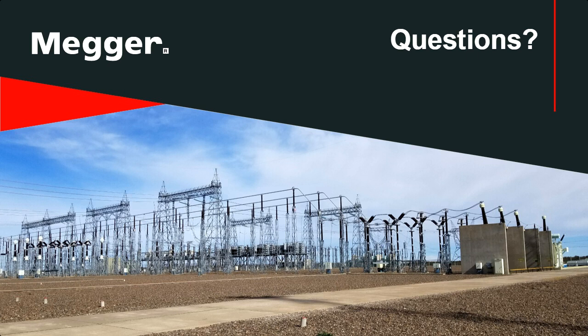All right. So as far as new installation, yes. This is a commissioning test, acceptance testing, right? You want to make sure that your breaker is going to operate how it's intended to operate. And this is the only way to check it, right? You can also perform power factor testing on these higher voltage breakers as well, with the contact resistance, insulation resistance, and high pot testing if needed, other than just the contact timing. So whenever you're asking, should you do this during commissioning? Absolutely, during commissioning and during your regular maintenance intervals.